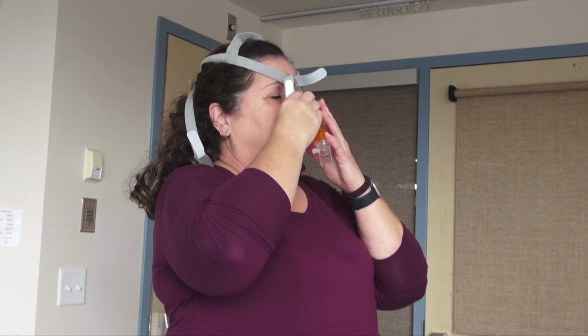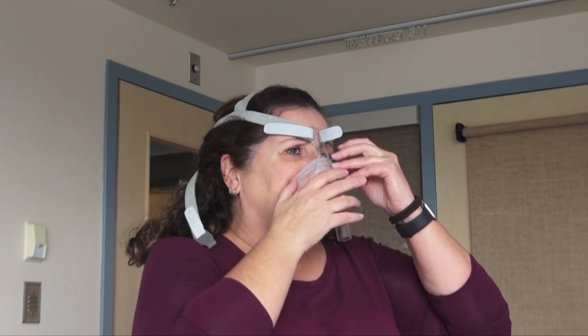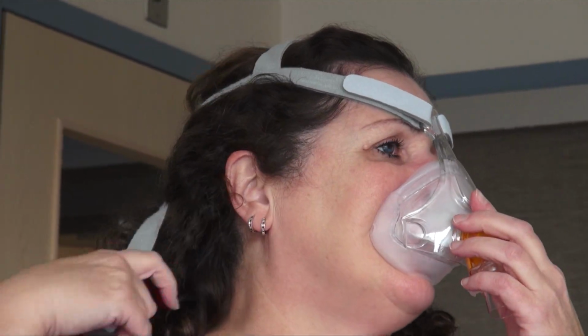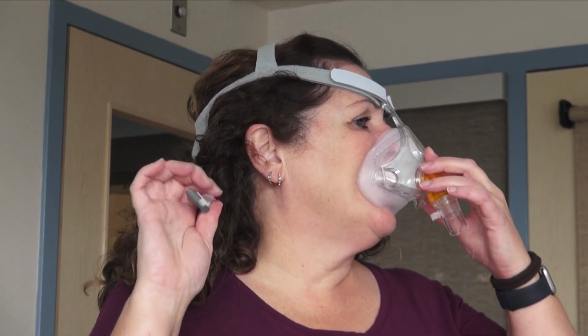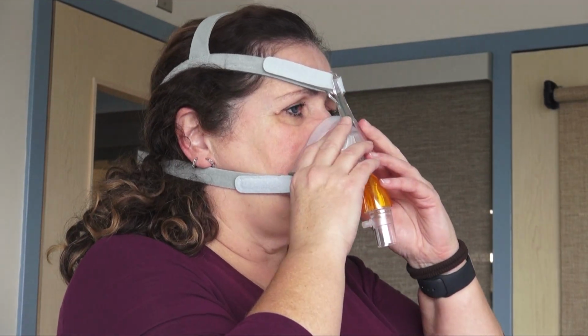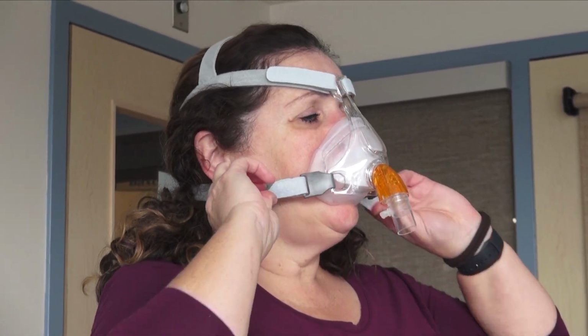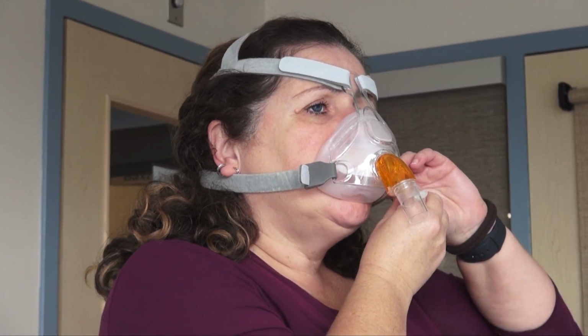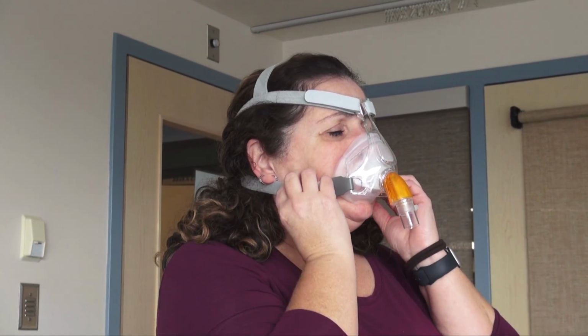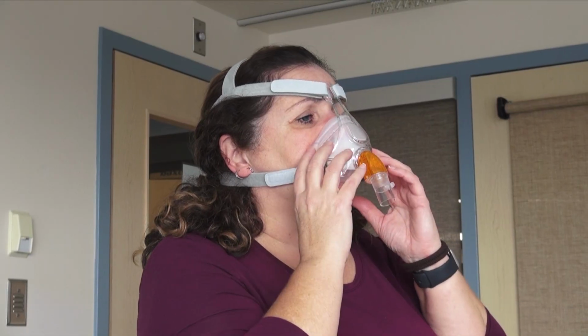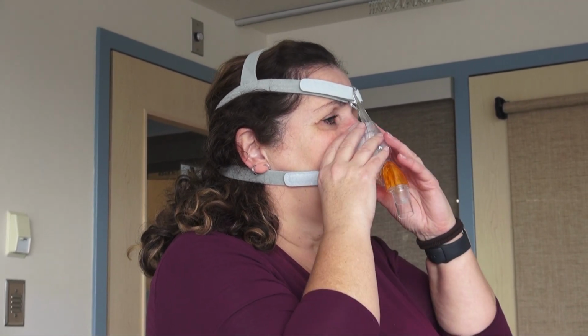And you can see that the top is already a little too tight, so I'm going to loosen it off. And now I'm just going to tighten off these ones here. Make sure the clips are going to clip in properly, not twisted. Okay. And you want it snug, but not so snug that it makes a mark on the nose. So you may end up adjusting this a little bit. Once you have this adjusted and you trial it on the patient, and you don't find any leaks around the eyes or around the chin here, then you know you have a good size.